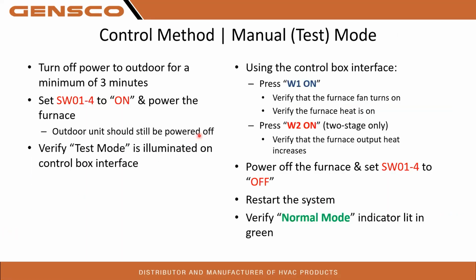And here is the test mode operation, how to do that. In order to get it into the test mode, you're going to turn your power off to your heat pump for about 3 minutes. And then after that, you're going to set SW01 number 4 to the on position and power the furnace back on. Outdoor unit will need to remain powered off. Verify test mode is illuminated on the control box, and then you can use the W1 and W2 on the control box to test the first stage and second stage gas furnace, if available on second stage.